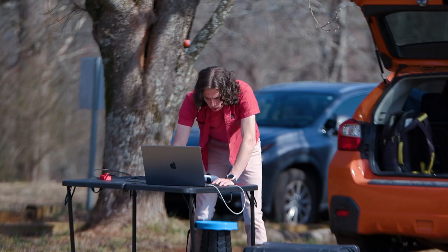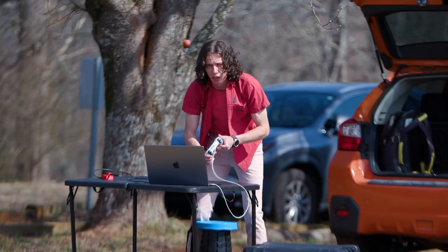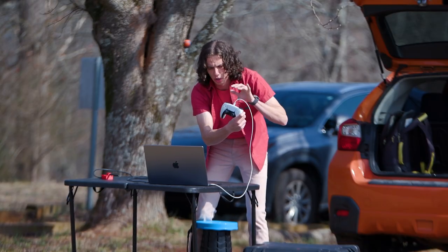Nonetheless, the default values are 1750 and 1250, with the neutral being 1500. So if we want to adjust the speed that we're lowering down the revolver or raising it back up, we can adjust these further away from 1500 to increase the speed, or make these values closer to 1500 to reduce the speed.